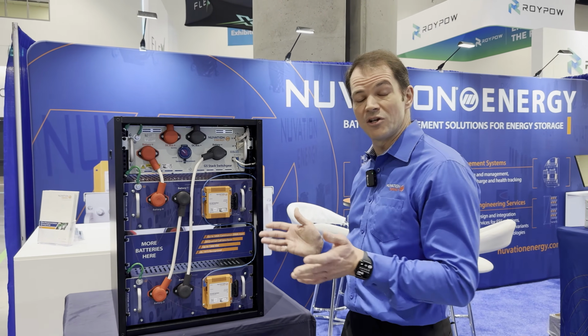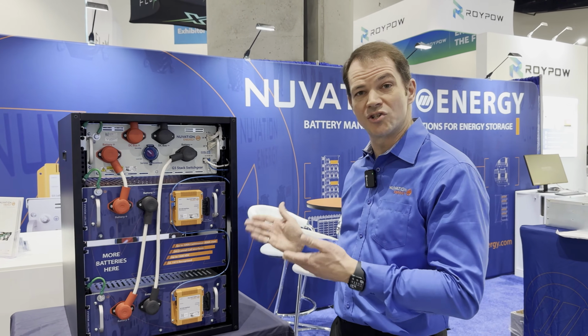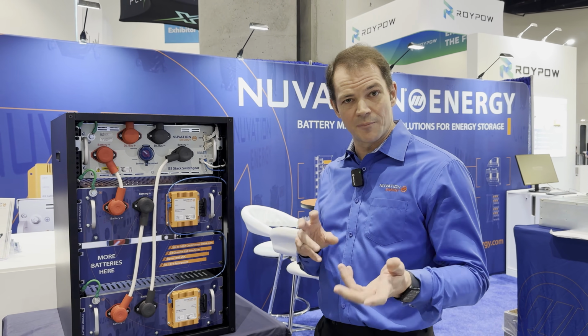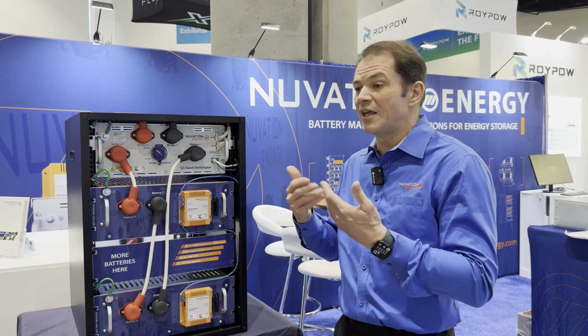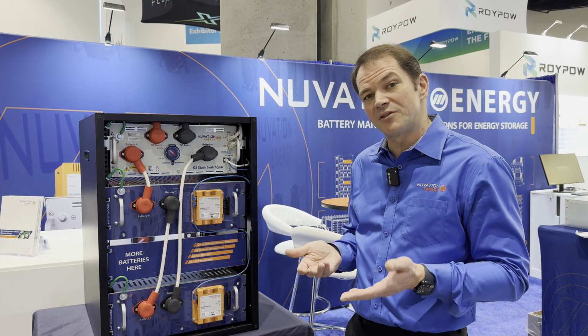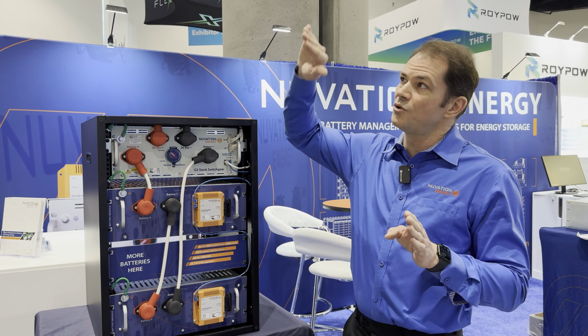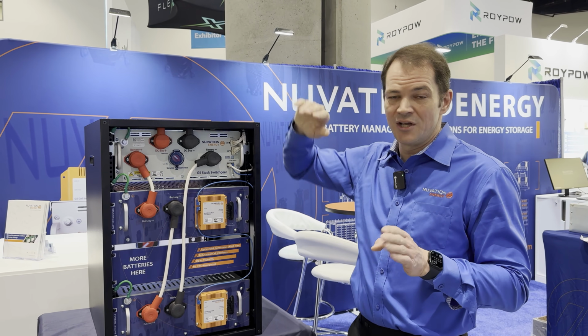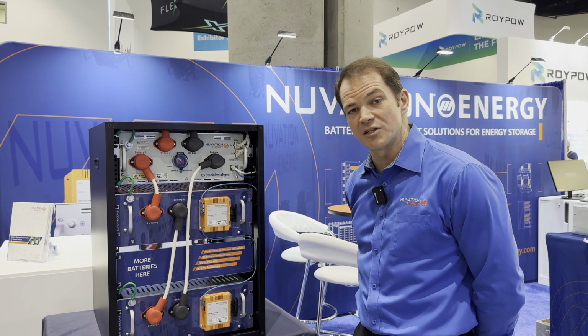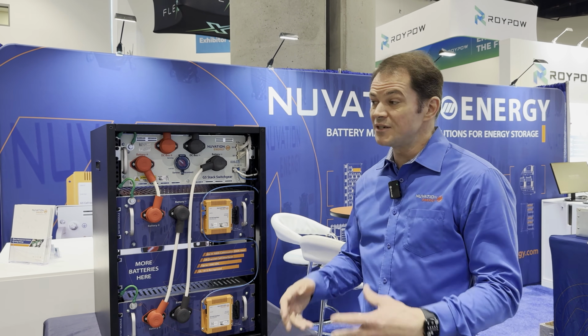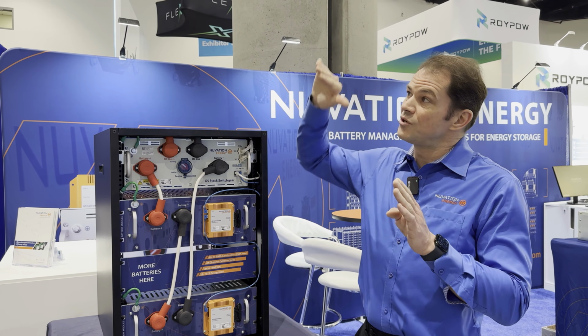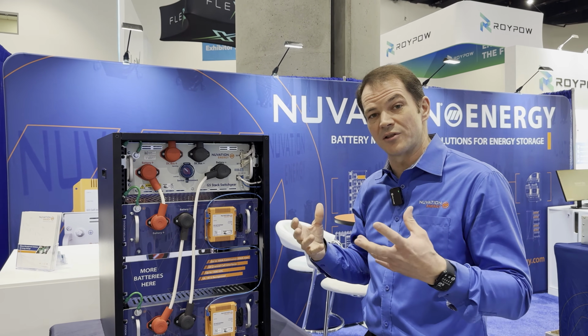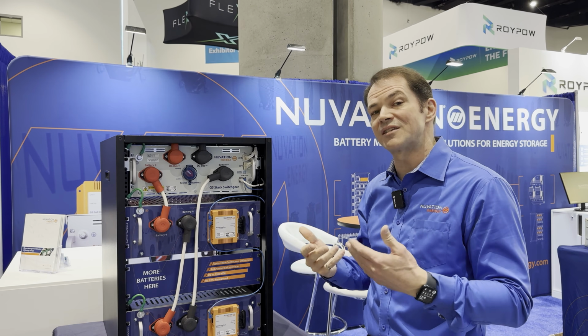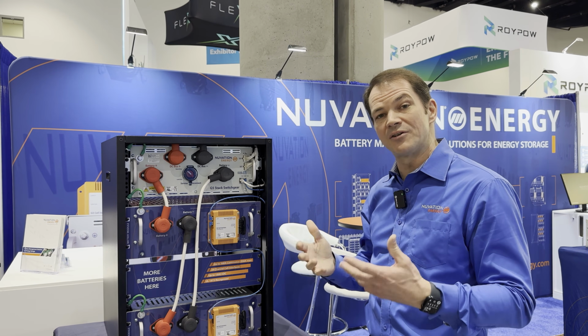What we noticed in operating systems was that if you only use voltage-based passive balancing, you can only do that balancing when you hold the system at a high state of charge. So instead, we invented a new system called continuous balancing — an algorithm that, when you get up to that high point, takes a snapshot of the system, and the system estimates how much charge needs to be balanced.